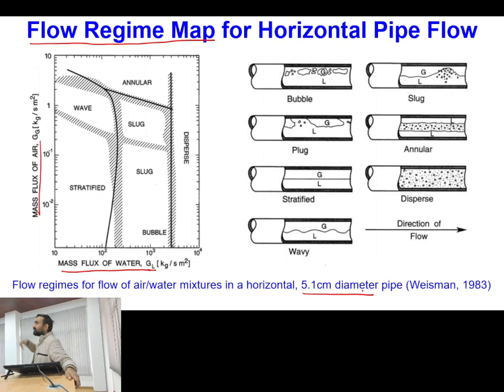In the pressure signal, if we see the fluctuations, of course for each type of flow distribution there will be a separate nature of the pressure fluctuations. If we perform some spectral analysis and try to find the dominant frequencies, then we can see that this set of frequencies is dominating in this regime. So if my pressure signal has a particular dominant frequency fluctuation, then I can say this regime is present within the pipe. That is the system which is non-visualization based.